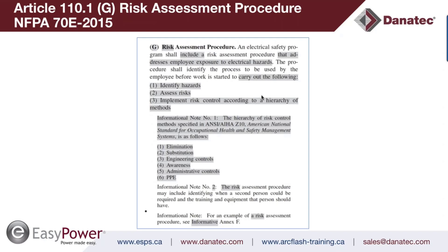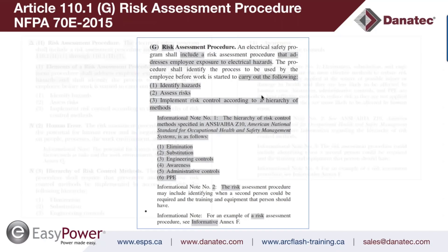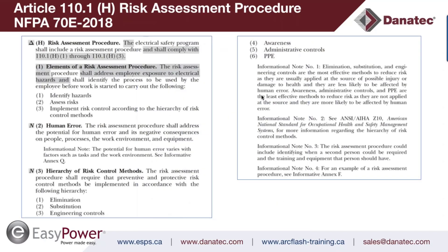The mistake in industry has been a bottom-up approach to applying control methods because the focus was on hazard and PPE, which is at the bottom of the hierarchy. In reality, 70E and Z462 say we need to de-energize first as a priority, then justify energized work, and then with the risk assessment procedure look at the remaining controls to reduce the inherent or initial risk level to a residual risk level that is as low as reasonably practicable.